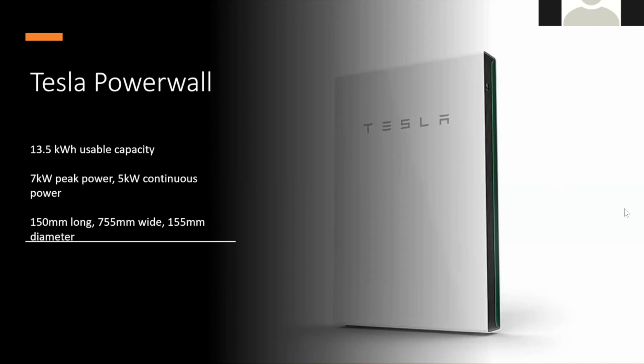The weight of one of these, they're pretty heavy, about 251 pounds for one battery. So all of these specs are something to keep in mind in terms of where, if you're thinking about purchasing one of these, the best spot would be. I think typically we're finding the basement's going to be the best because, number one, it's usually close to your main electric panel, and number two, the temperature really doesn't get below freezing down there in the winter.